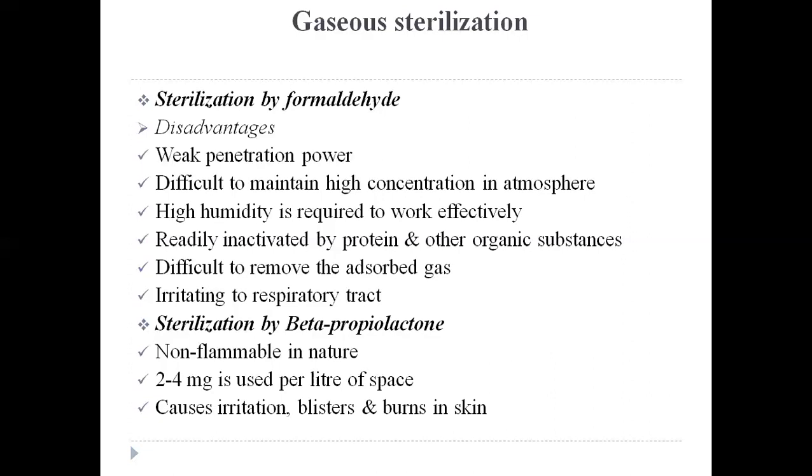Formaldehyde is basically an alkylating agent which was used to sterilize some special chambers in hospitals and to sterilize catheters, syringes, and other thermolabile substances which degrade in presence of heat. So those things can be sterilized by using this formaldehyde gas. However, nowadays the use of formaldehyde has been restricted for sterilization purposes, and it is only used in certain cases like in the fumigation of empty rooms and after infectious diseases.